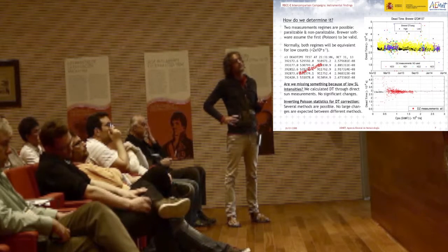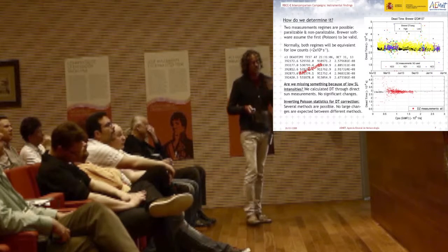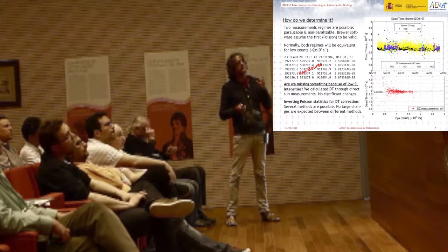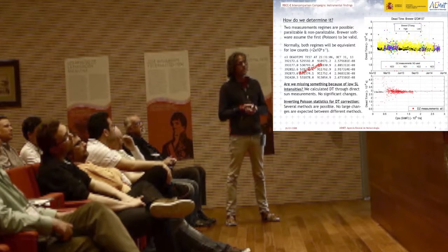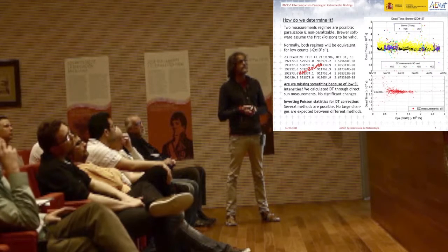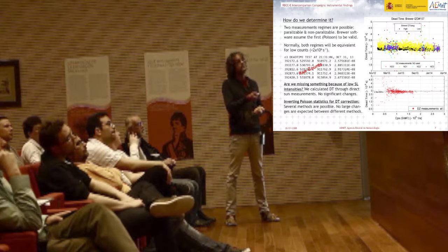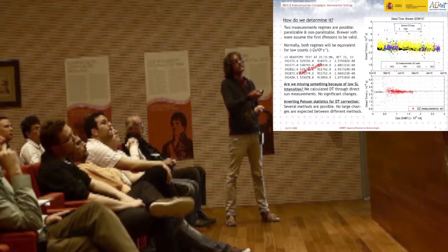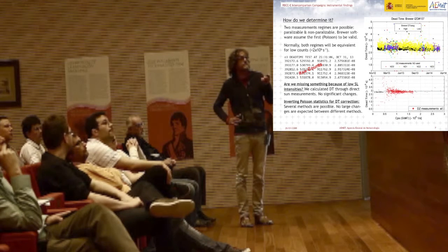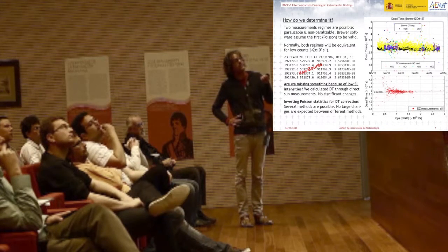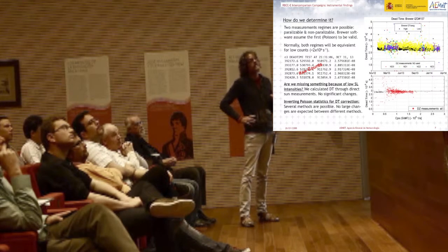So we modified the DS routine to make measurements on all slits, on slit 7 and 2 and 4. And we perform the same calculus as the Brewer does to calculate the dead time. And this is the result. We show the result in this plot. We see here the squares, the yellow and black squares, refer to the normal DT average file.